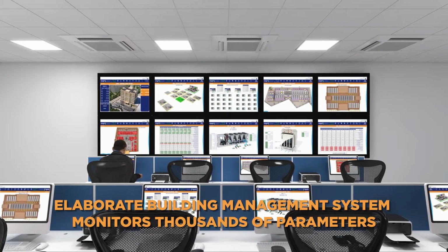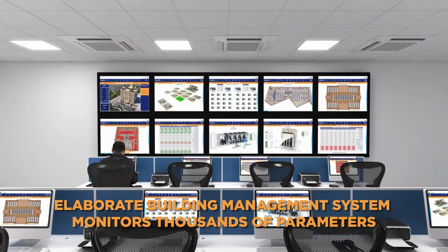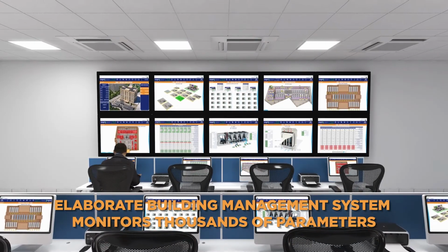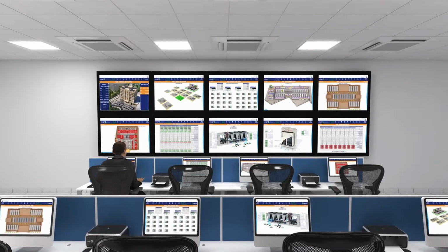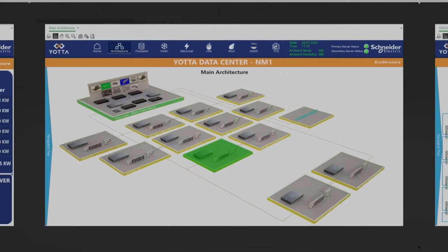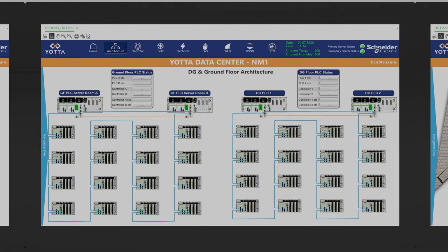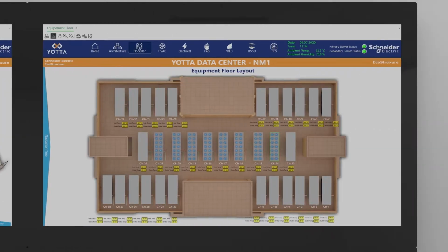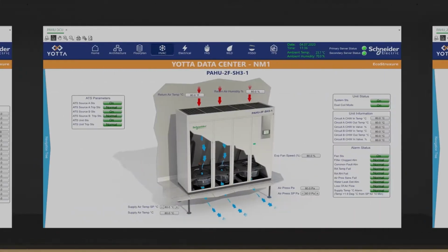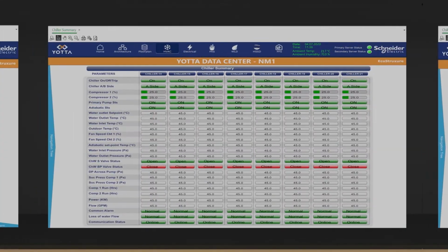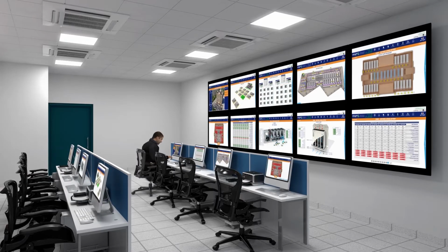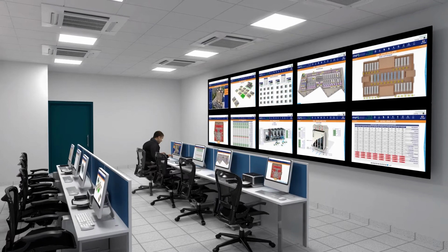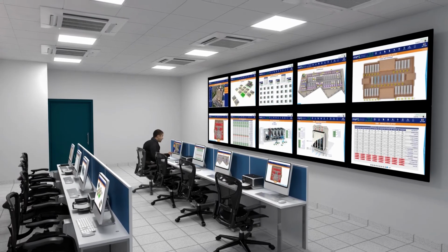A state-of-the-art, feature-rich, and redundant building management system, or BMS, monitors Yotta NM1. Thousands of parameters from every single utility device, including transformers, diesel generator sets, fuel capacity, HT panels, cooling, and power, are monitored by the BMS. Select customers can request remote BMS logins to monitor their setup in real time.